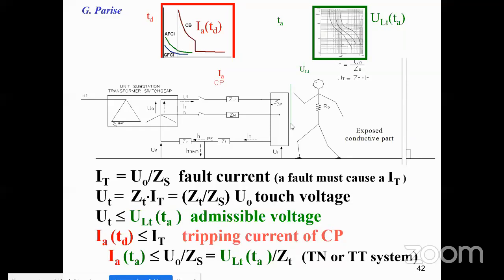And so in the last line, we show the condition suggested by the IEC approach. You can see Ia, in the time ta, has to be lower than the fault current. The fault current is the current of the system when the exposed conductive part is faulted. So the tripping current has to be lower than the fault current, but the trip has to operate in a time lower than or equal to the admissible value.